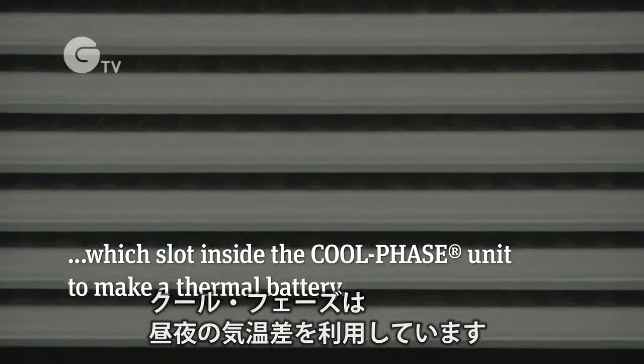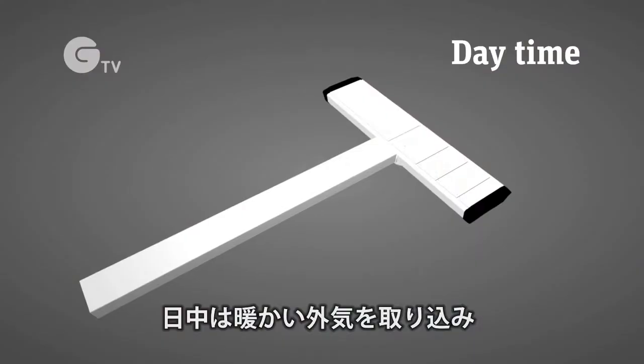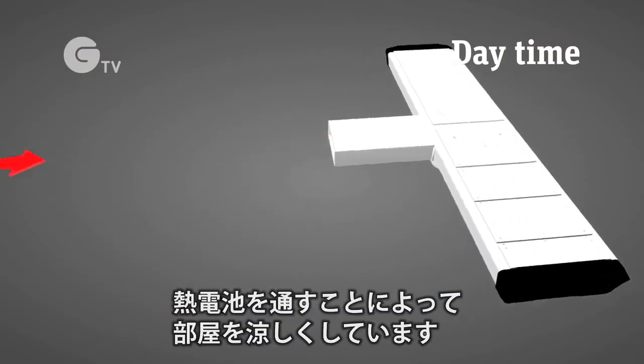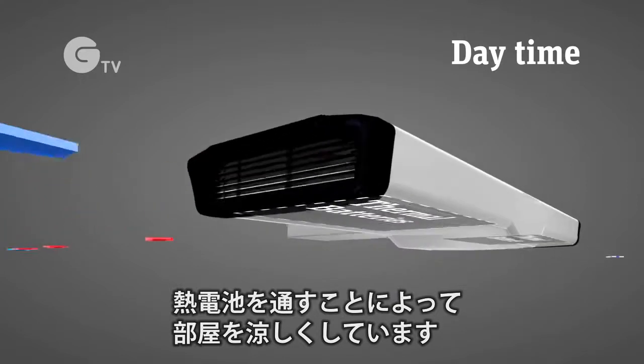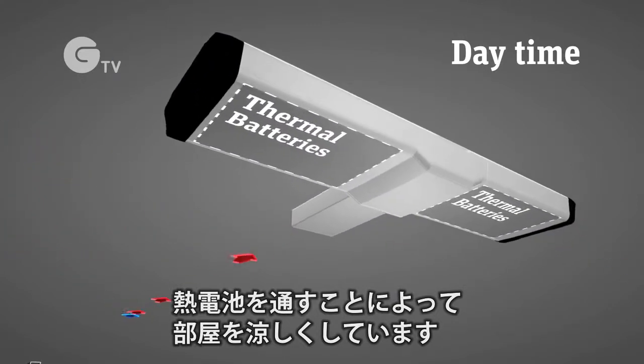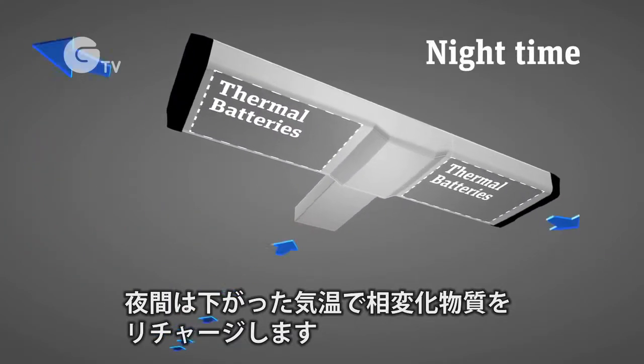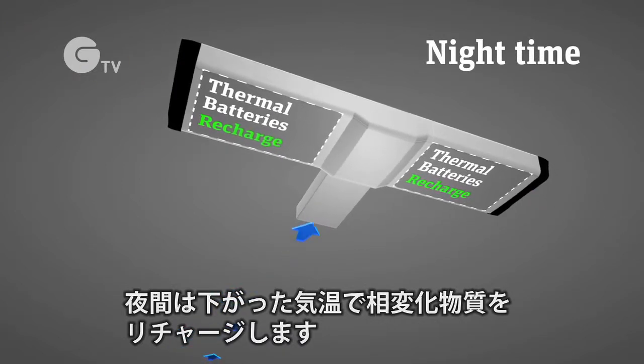CoolPhase makes use of the difference between daytime and nighttime temperatures. So during the day, we're taking warm external air, passing it through the thermal batteries, which are absorbing that thermal energy and thus introducing a cooling load to the room. During the night, we rely on the cooler nighttime temperatures to recharge that phase change material.